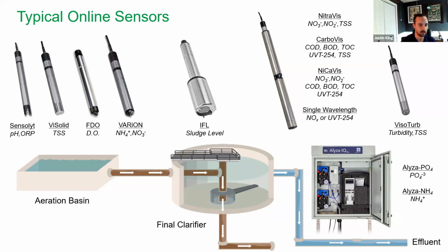So for at least our product portfolio or our suite, we can measure a wide variety of parameters. This includes pH and ORP, total suspended solids, dissolved oxygen, ammonium and nitrates, even sludge level using an ultrasonic sludge level sensor. And then we have a suite of UV sensors, which is this big one in the middle here, which can measure a host of different parameters, including nitrate, nitrite, TSS, and a lot of different carbon parameters, including COD, BOD, TOC, and then of course, since it is a UV measurement, we can do the traditional UVT 254 measurements.